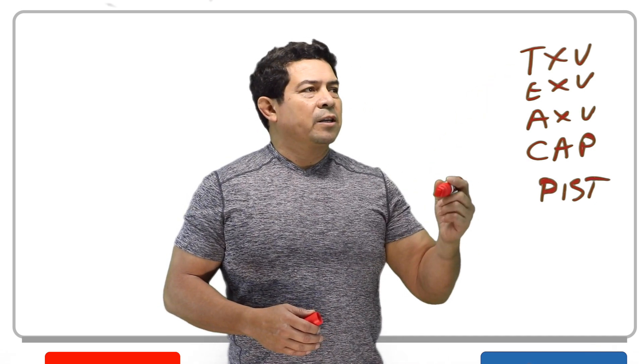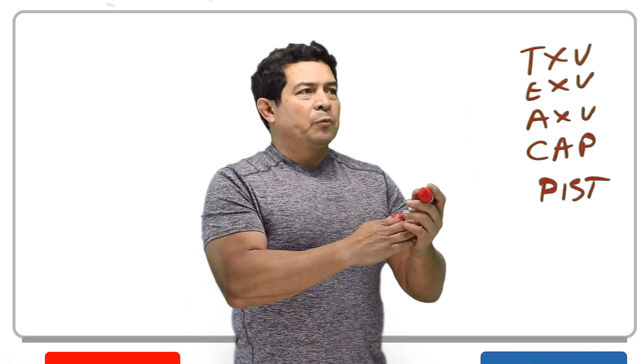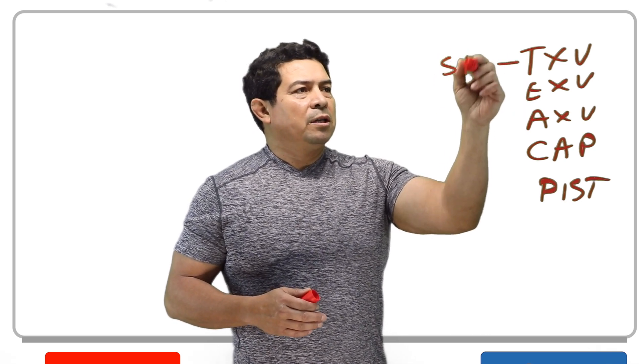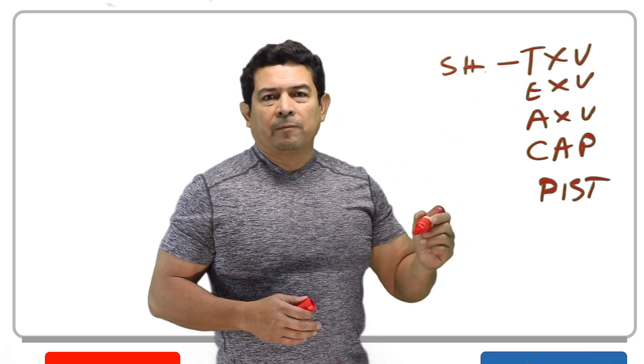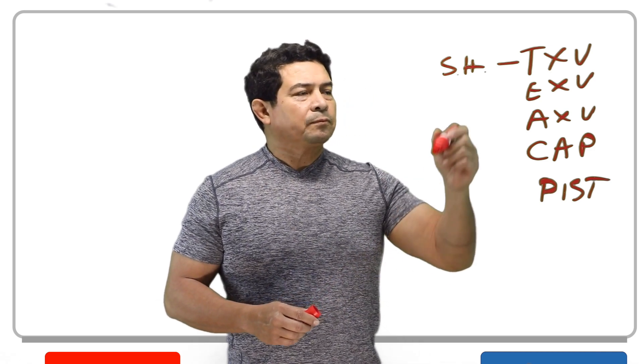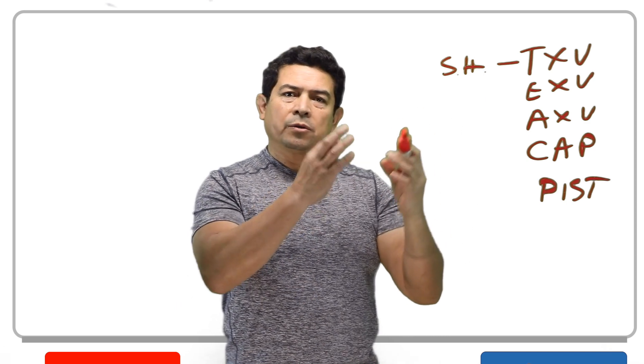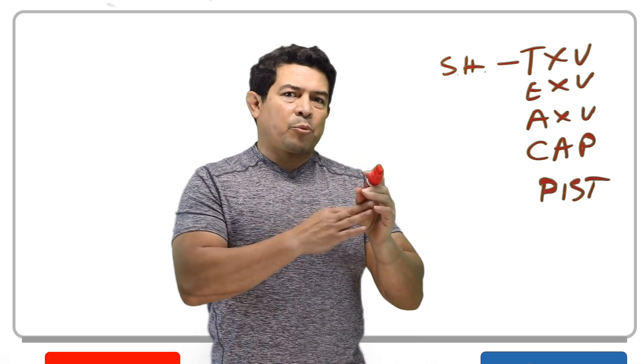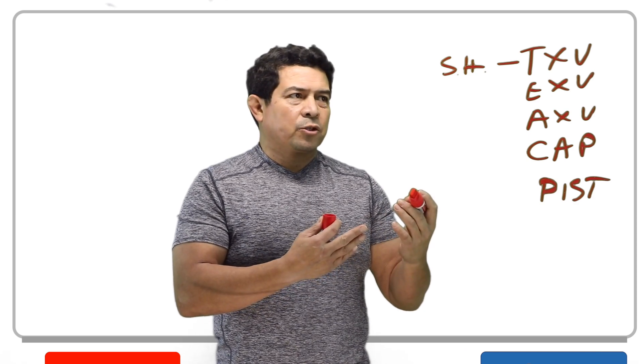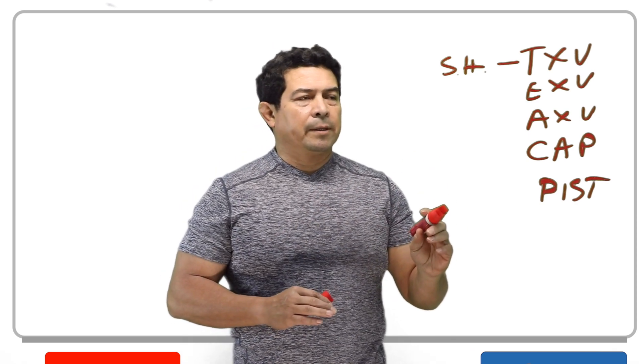The thermostatic expansion valve — it has to do with temperature, but actually what it does is it maintains superheat in the evaporator. It makes sure that the superheat in the evaporator is right where it's supposed to be. It's going to open and close to maintain that proper superheat. They usually come preset from the manufacturer, but sometimes we have to adjust them.